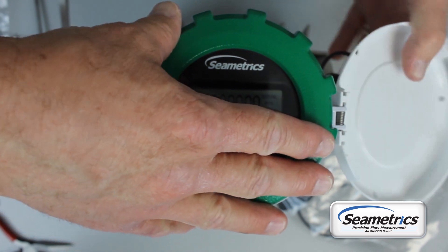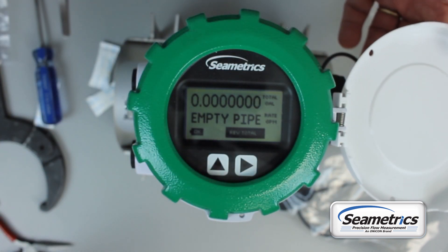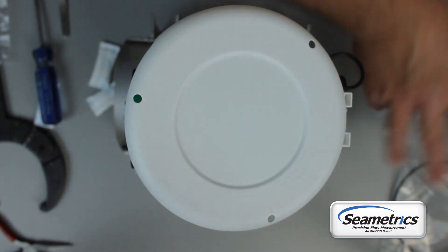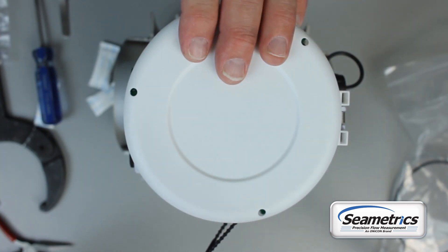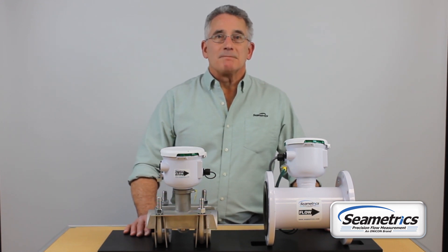Screw the lid all the way down. If you don't screw it all the way down, you're going to get moisture or dirt in there over time and it will destroy the meter. Once the o-ring touches, just give it a little tighten to compress the o-ring and give it a good sealing surface. In your battery replacement kit there is a security seal — if your meter needs one, connect the seal and you're done. That's all there is to changing the battery in one of our meters. For more information on this or other products, please visit us at Seametrics.com. Thanks for watching.